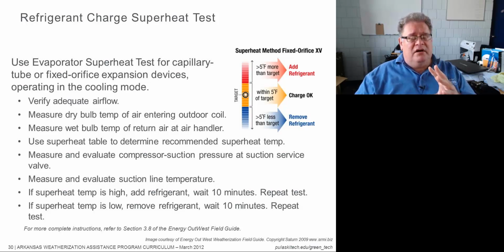But knowing whether or not this test is being run correctly is key to knowing whether you're getting what you're paying for. Are we testing an air conditioning system and condemning it or passing it because the test was invalid? That's not a good thing to do. So as a quality control inspector, we should understand how things were done. When we start seeing photographs of temperature probes that are either not wet bulb, or are wet bulb being taken at the wrong place under the wrong conditions, then we can start saying, this isn't right, okay?